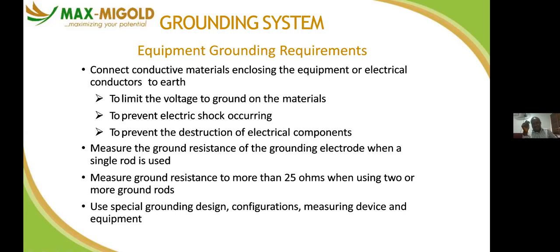Every 6 months. And the reason is, when you have partial contact, if you have a loose connection along your installation, that installation is compromised. So it will affect your ET. Maybe your ET cable is not firm to the DB or other appliances. That means there is no continuity. There is an open circuit. Your house is at risk. If you touch any metallic plate or any conductor, it can harm you or can even lead to death.